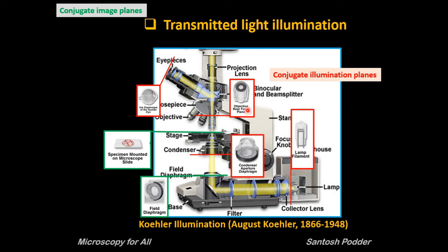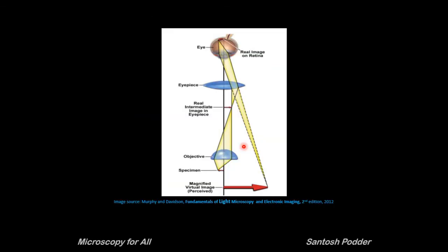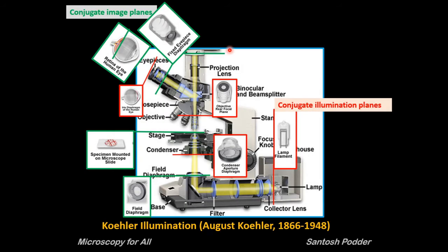After the light passes through the specimen it goes through the objective lens and forms a real intermediate image near to or at the eyepiece diaphragm. The eyepiece enlarges this small real intermediate image — it functions mainly as a magnifying glass for the intermediate image. Finally, the brain creates a virtual image with the help of photoreceptors in the retina and the optic nerves, and this we perceive as an image. If you want to capture the image, instead of going to the eyepiece, the light should go directly to the camera port where the intermediate image will be captured by the camera. In camera the image is magnified by the objective only — remember this point.